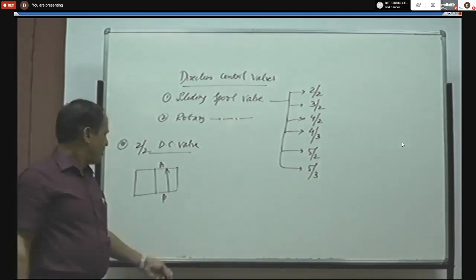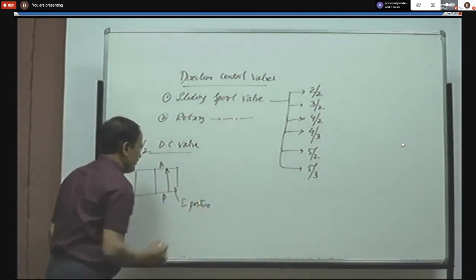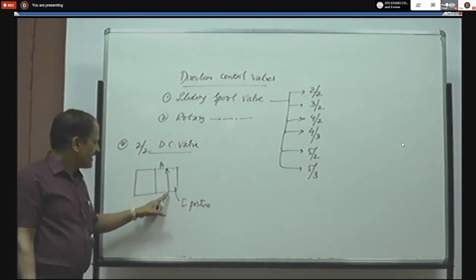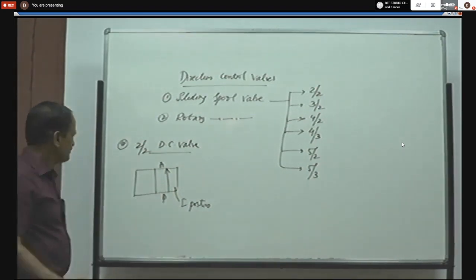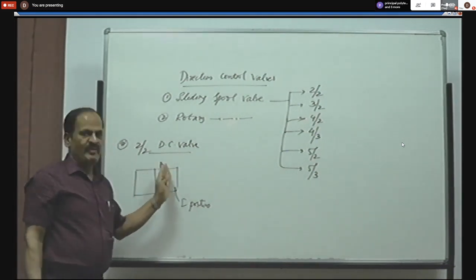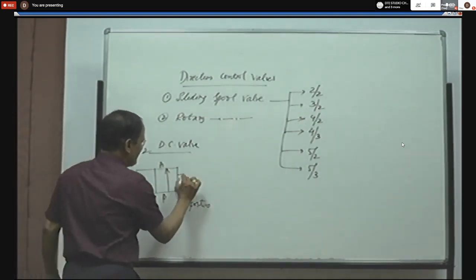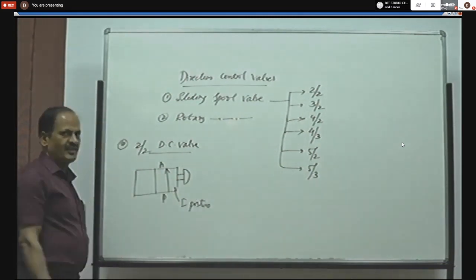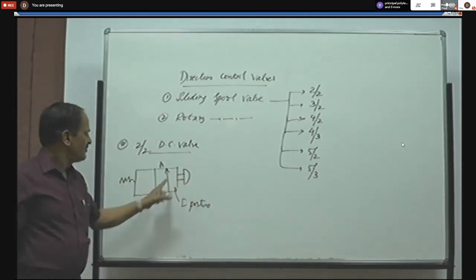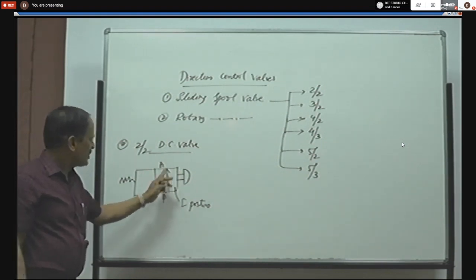The symbolic representation of a 2/2 DC valve: each position is represented by a box. Since it has two boxes, two positions are required to change the ports, and in each position there are two ports — port P and A. The direction of flow is represented by an arrow. In the first position, flow takes place from pressure port to the working port. A is the working port connected to the actuator; P is the pressure port connected to the pump. By pressing the push button, P and A are connected, so fluid flows from pump to the working port.